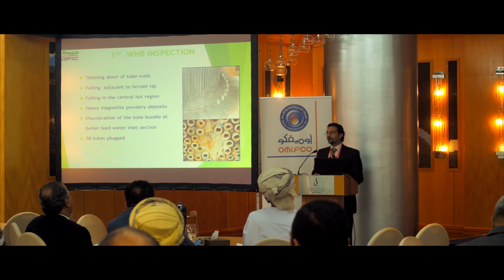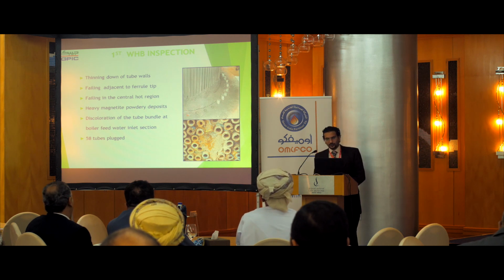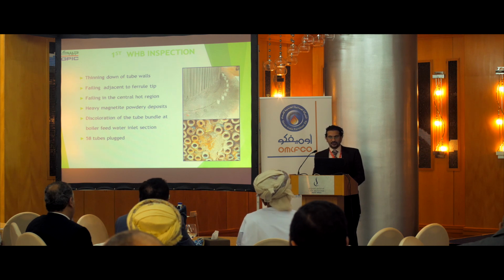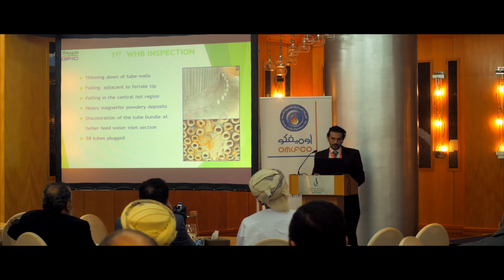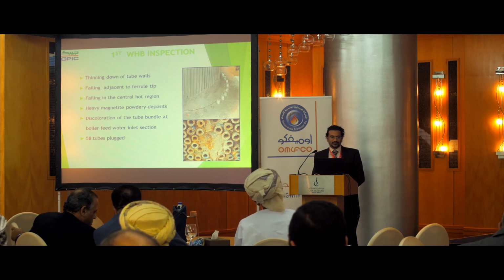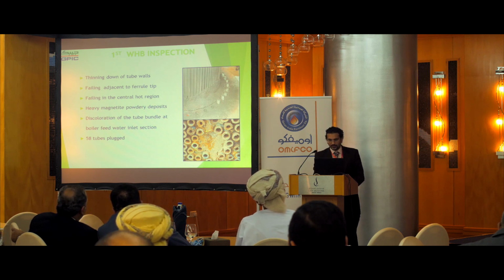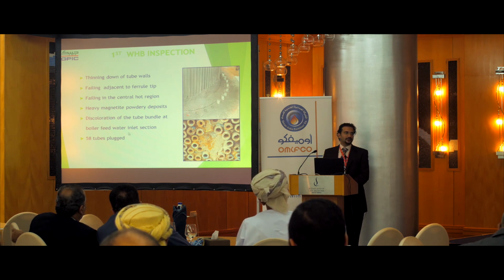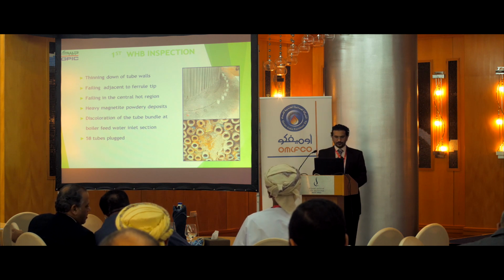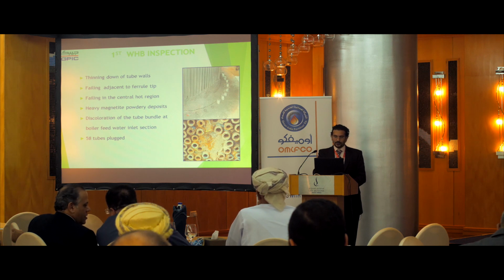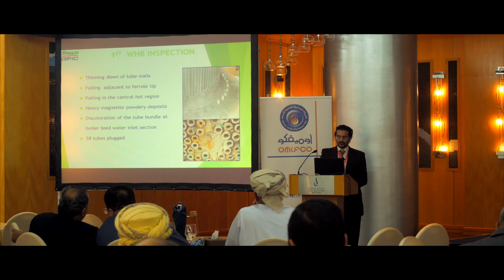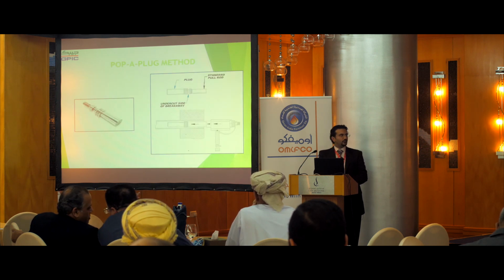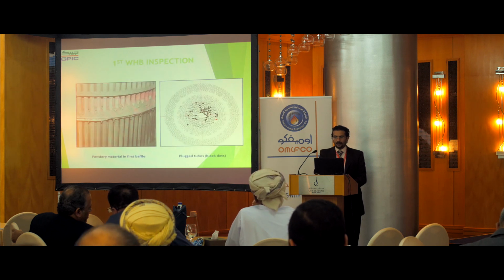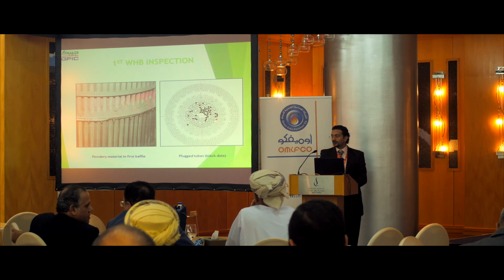After opening and inspecting our first waste heat boiler, we saw thinning down of the walls, failing adjacent to the ferrule tip at the tubes. This mostly was happening in the central hot region, with heavy magnetite powdery deposits, as we can see here in the photos, and discoloration of the tube bundle at the boiler feed water inlet section. After studies and going back to our providers, we said that we will plug 58 tubes using the Pop-A-Plug method. There are still photos of the first waste heat boiler. You can see the powdery materials in the first baffle.